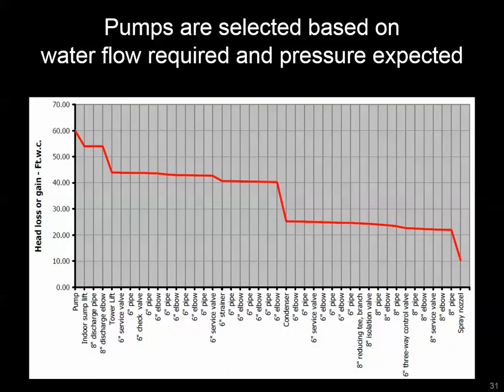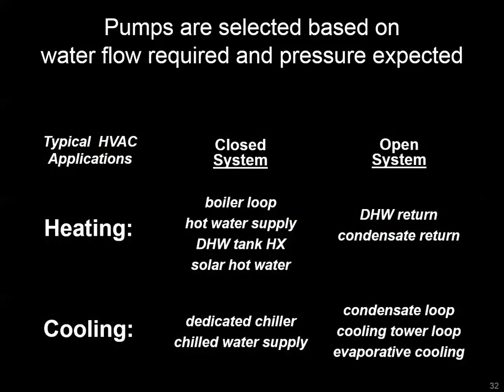If you remember one thing from this introduction, there are two key parameters for pumping systems: water flow and pressure. Water flow is determined by the heat load that needs to be met at the plant and zone. Pressure is determined by all the individual components and piping in the pump loop. Visualizing this: as you leave the pump at high pressure, every length of pipe and every component creates an incremental pressure drop, and the sum of all those drops is the pressure the pump must output.